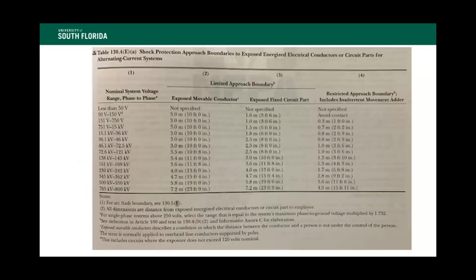And here's a picture of that table, straight out of the standard. As you can see, if you look up here at the very top of this list, less than 50 volts, not a problem. We don't worry about it. In fact, 70E really doesn't apply to voltages or systems less than 50 volts. But let me ask you this. Can that less than 50 volts cause a spark? Can it cause an arc?